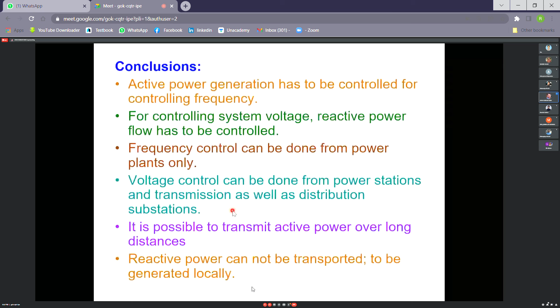Because of this, there is more reactive power in the system at the receiving end side. If we connect a shunt reactor to it, what will happen? The reactor will absorb that extra power in the system, so that the voltage comes down to its nominal value. Because if the voltage increases at the receiving end, then the bus bar insulation and all those things would be heavily taxed by the increased voltage. Understood? So from this knowledge, we can think of voltage control occurring in this way.